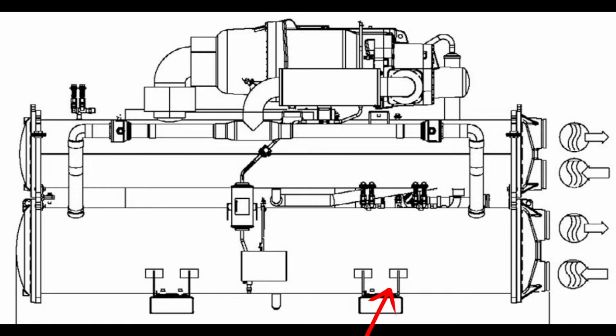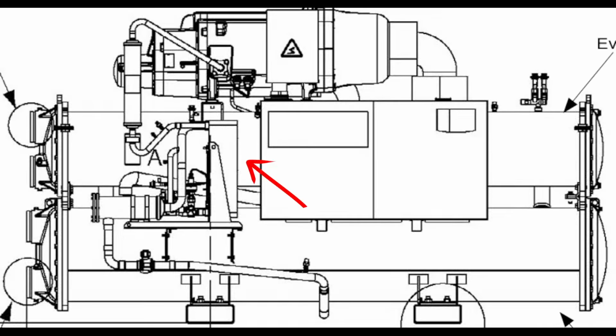And I do know that there is a little pipe here and a pipe here that connects into the bottom of the condenser. Again, this would be something I'd have to dive into, what are these serving in this process. Maybe that has something to do with, hey, we're running really high condenser pressures and condenser water temperatures with this machine because it's a water-cooled heat pump. Or not water cooled, but because it is a heat pump system. So that might have something to do with it. Again, we'll come back to that.